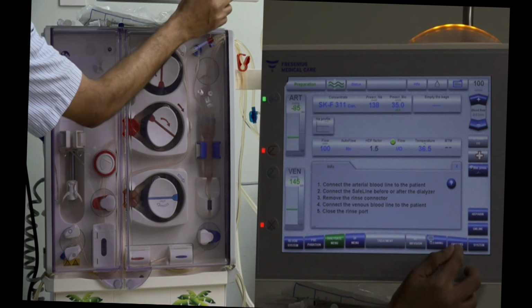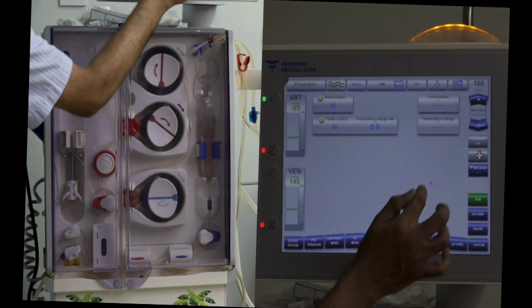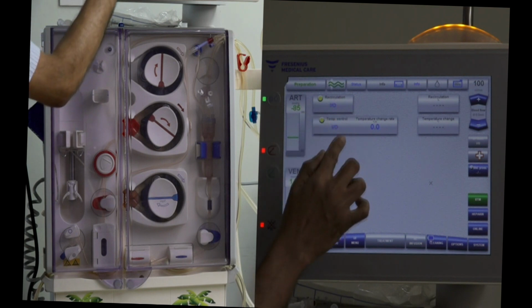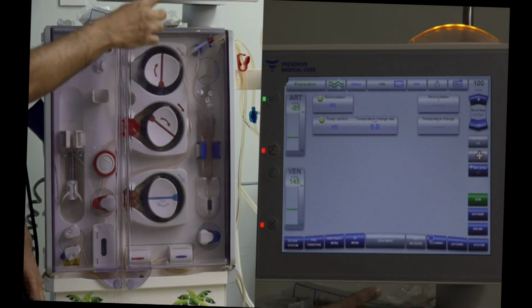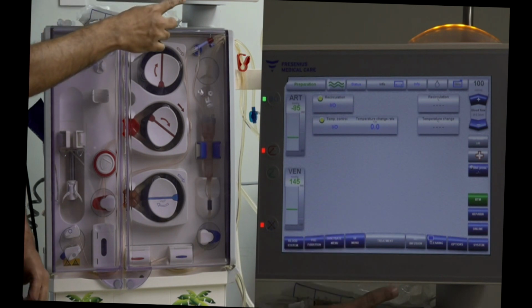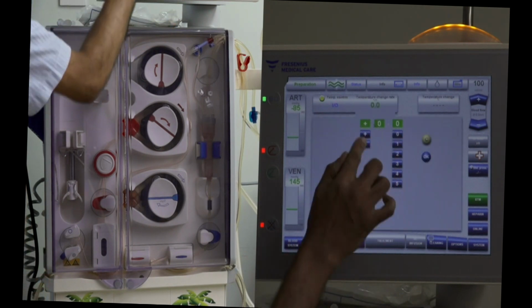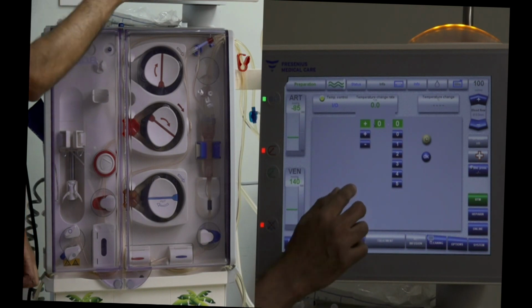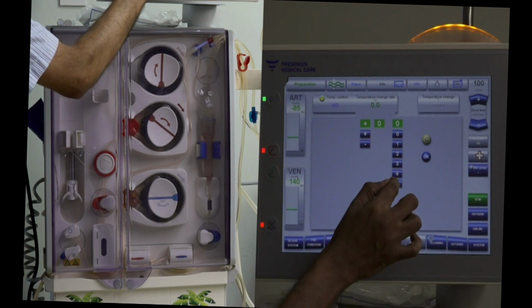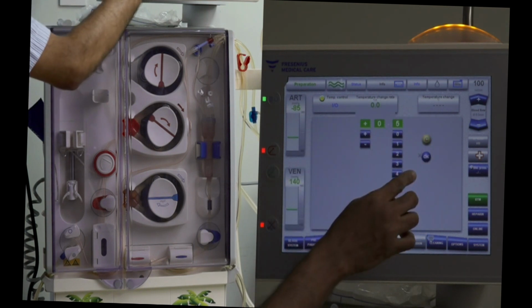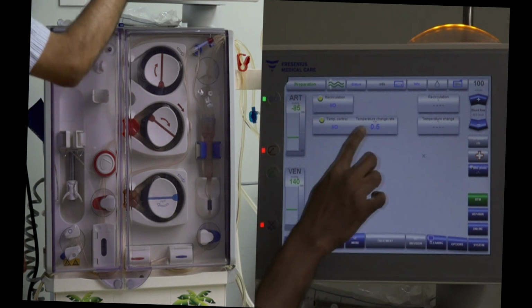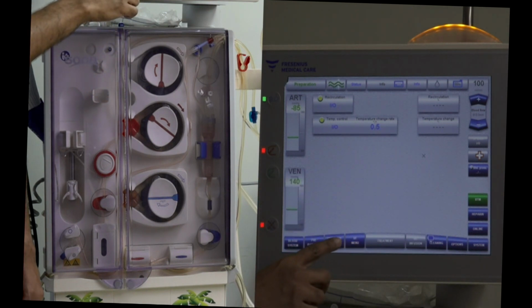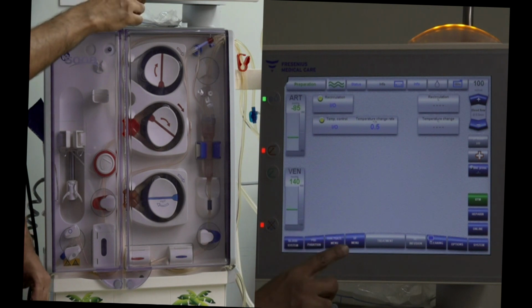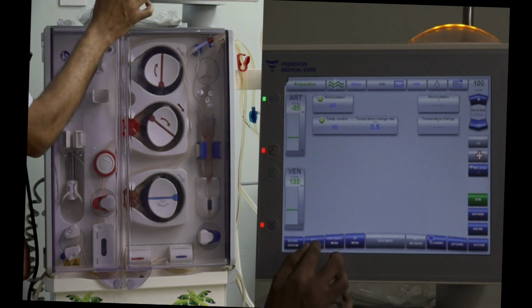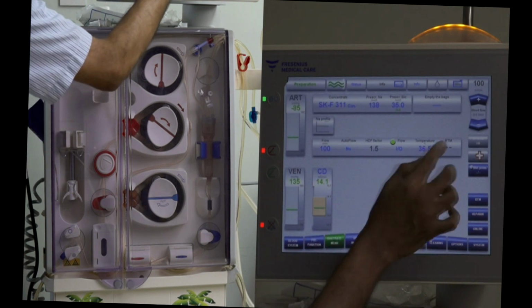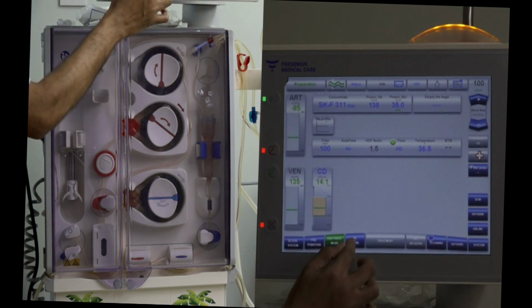If we were to choose the option of using the blood temperature monitor, then we could switch on recirculation and temperature control. Once we do this, the machine will automatically adjust the dialysate temperature depending on the temperature change between the arterial and the venous line that we are prepared to accept, which is a maximum of 0.5. So once I set this to 0.5, the machine will ensure that the difference between the arterial and the venous line temperatures will be 0.5 degrees, and it will do this by adjusting the dialysate temperature automatically. So now the dialysate temperature during treatment will be automatically adjusted.